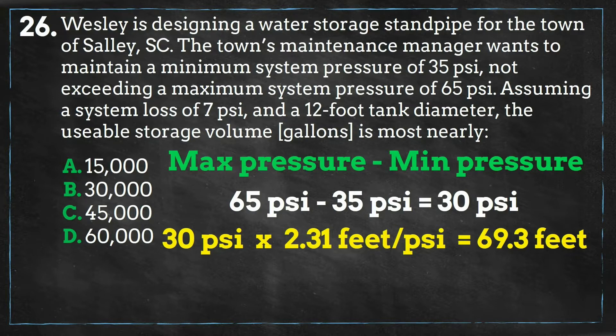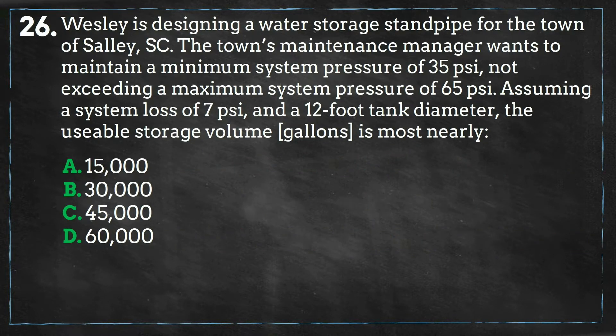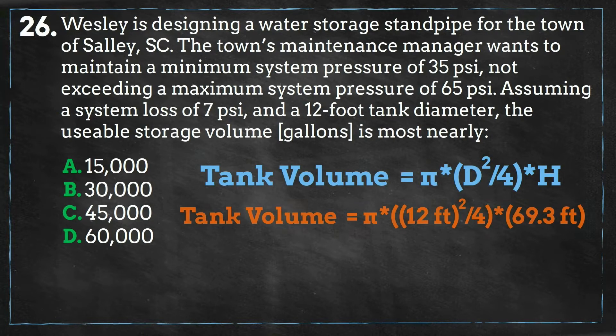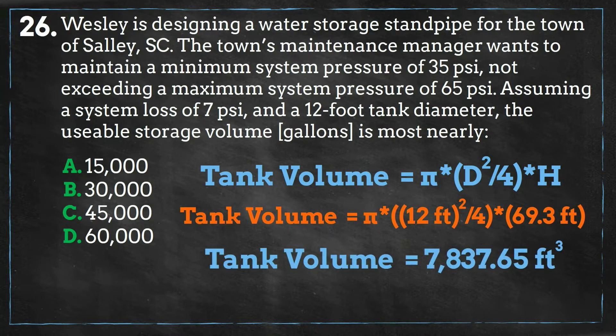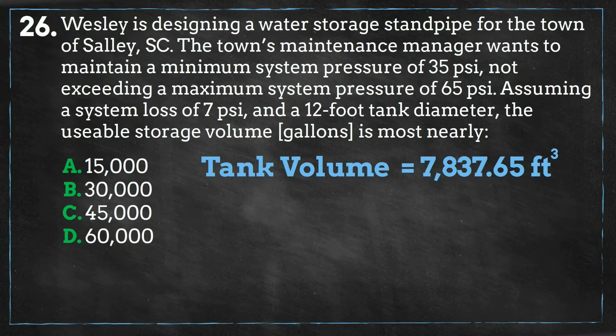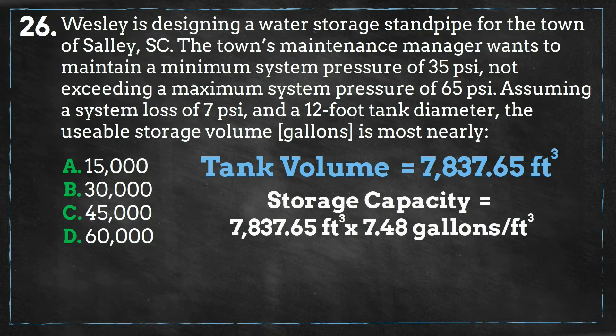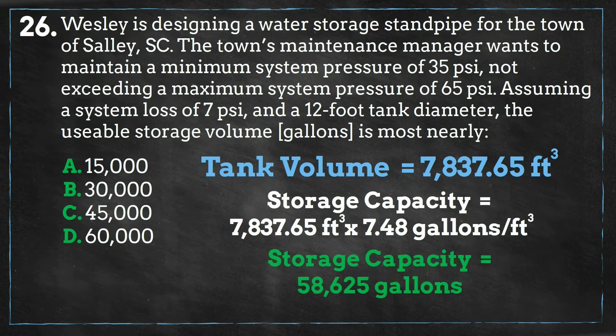Now that we have the tank's height along with the diameter, we can solve for the volume of the tank, and we get approximately 7,838 cubic feet. Using the water conversion of 7.48 gallons per cubic foot, we multiply this by the tank's volume and get 58,625 gallons, which is closest to D.